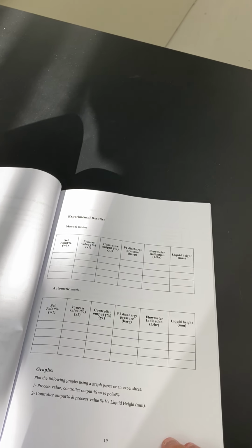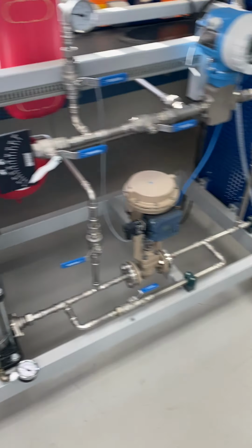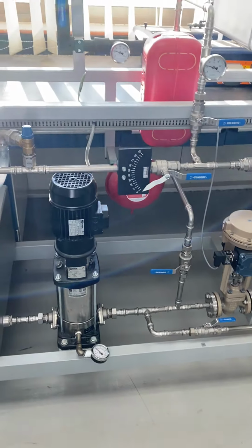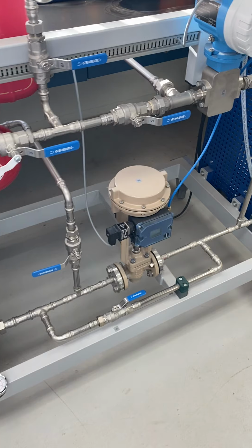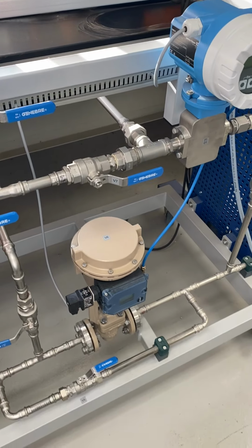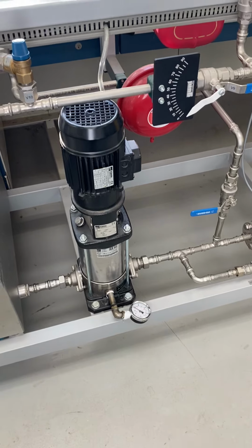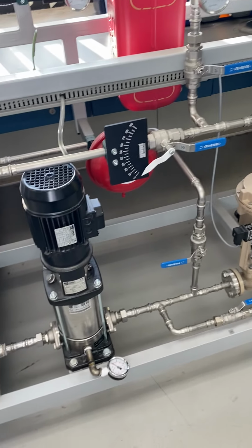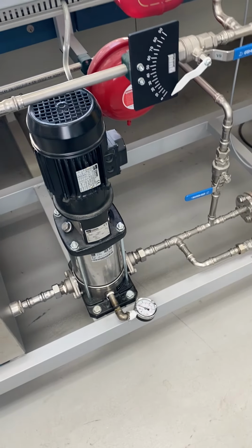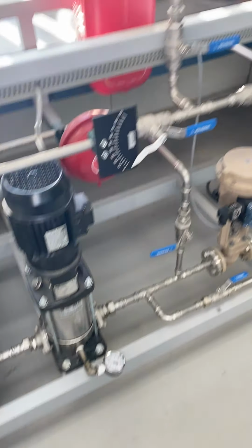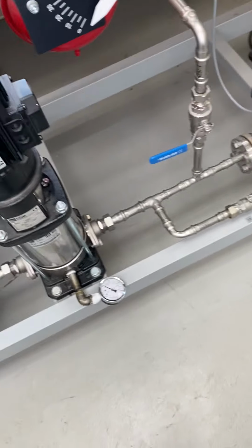Along with that, we will look at the discharge pressure of the pump, and that will be slightly different from what we have seen during the flow rate experiment, guys. In the flow rate, if you remember, the pump was running at a fixed speed, 100% maximum speed, and the flow was adjusted using the control valve. Okay, so during that time, we have seen that as we increase water flow rate inside the system, the discharge pressure of the pump was decreasing. But in this experiment, we are not using the control valve. Actually, water is being bypassed.